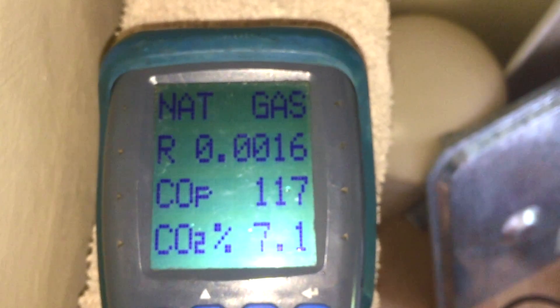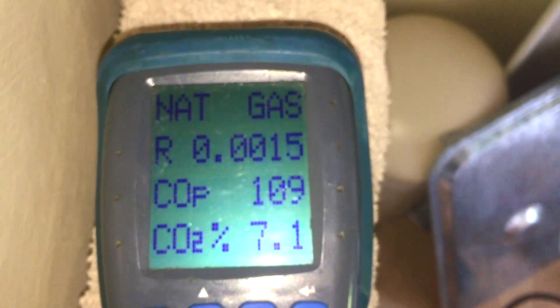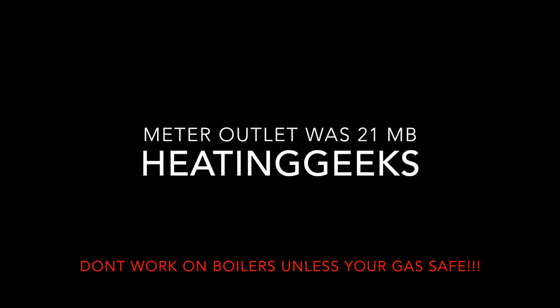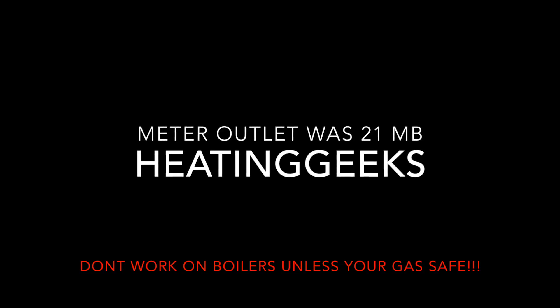10 liters a minute - if you look at that you would not expect that boiler to have an inlet pressure that low and be operating this well. I made this situation safe. I haven't heard back from the customer but she did seem like she was going to get it done - I suggested a couple of guys to her to sort that out, hopefully it's been sorted.